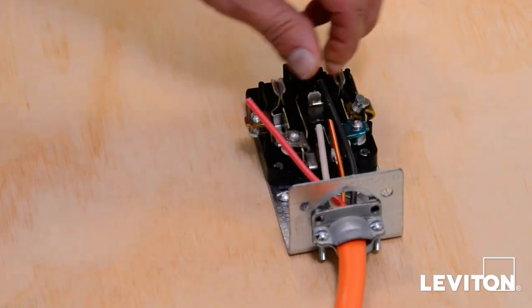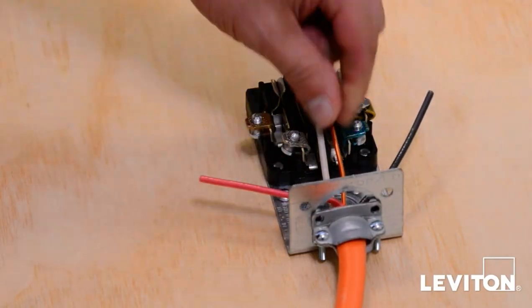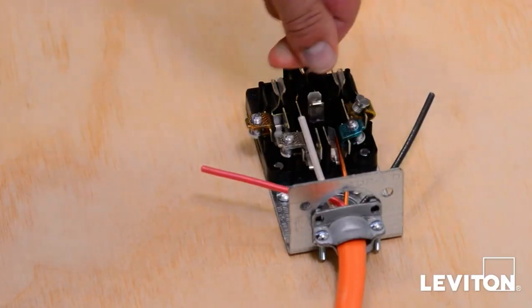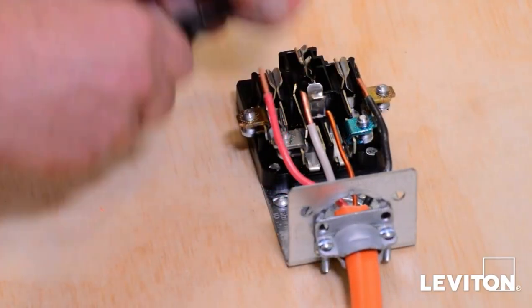In this instance, we are using 10 gauge wire. The product accepts 10, 8, 6 and 4 gauge wire. Strip wire leads to 11 sixteenths of an inch. A strip gauge is located on the base to ensure the proper length.